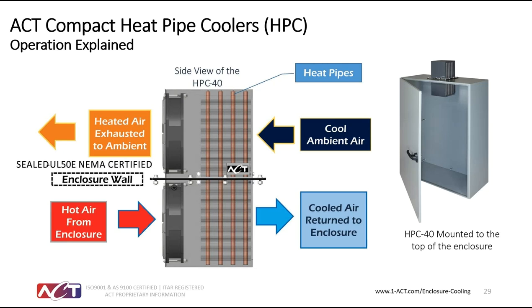And again, you have the hot air on the inside of the cabinet blown across those heat pipes, and because we're rejecting the heat to the outside, those heat pipes become cooler and cooler. As the fan is blowing on the inside, the air going from the left to the right becomes cooler on the inside of the cabinet. And then the cool air on the outside of the cabinet is rejecting the heat that's being transferred by the heat pipes. And because it's on the outside, again, we don't care that the heat is being rejected out there. We want to get rid of that heat inside the cabinet.